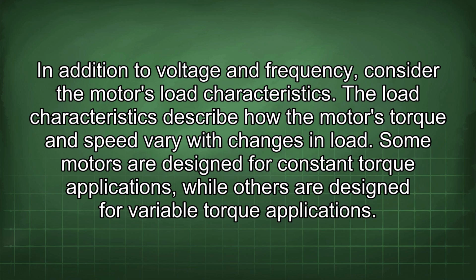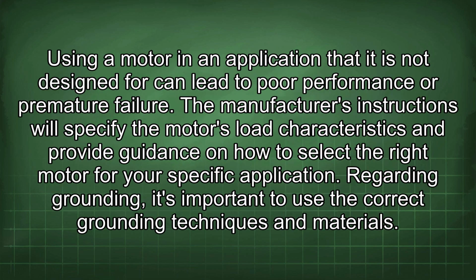In addition to voltage and frequency, consider the motor's load characteristics. The load characteristics describe how the motor's torque and speed vary with changes in load. Some motors are designed for constant torque applications, while others are designed for variable torque applications. Using a motor in an application that it is not designed for can lead to poor performance or premature failure. The manufacturer's instructions will specify the motor's load characteristics and provide guidance on how to select the right motor for your specific application.